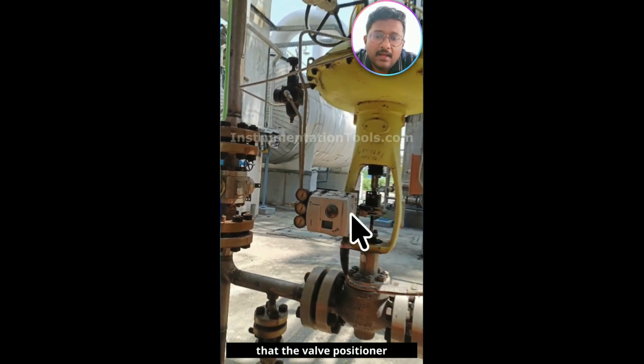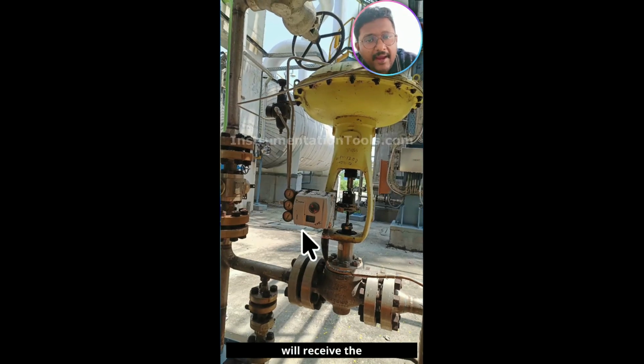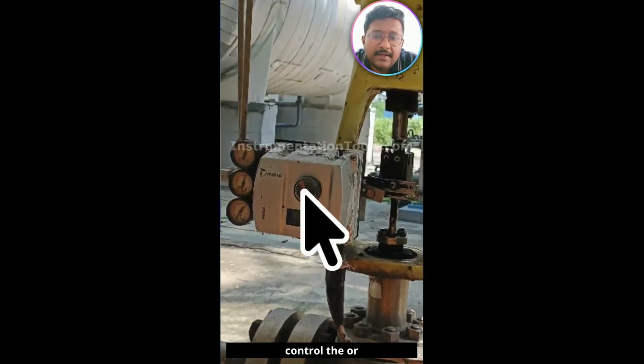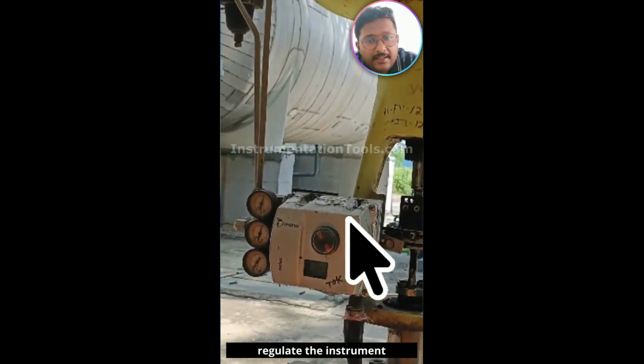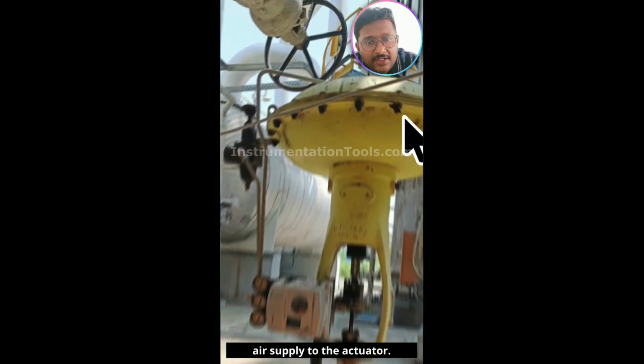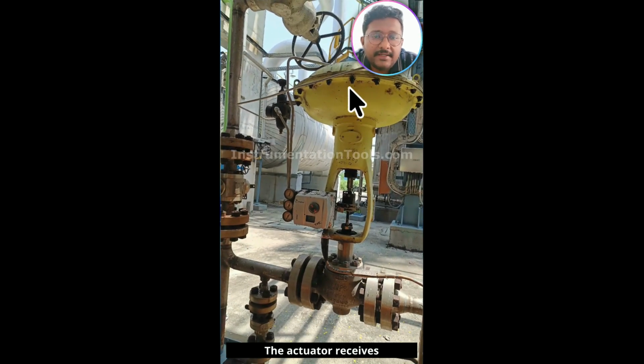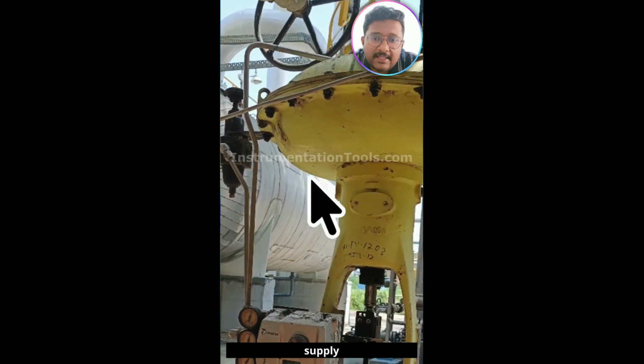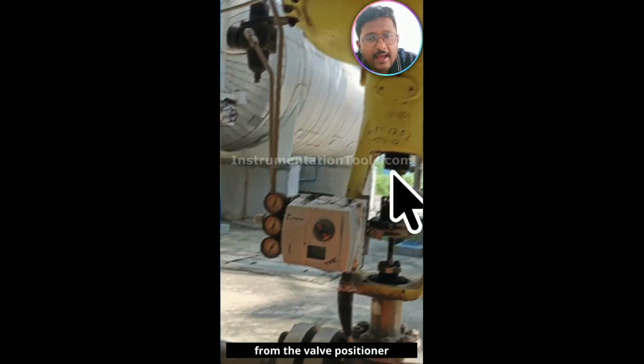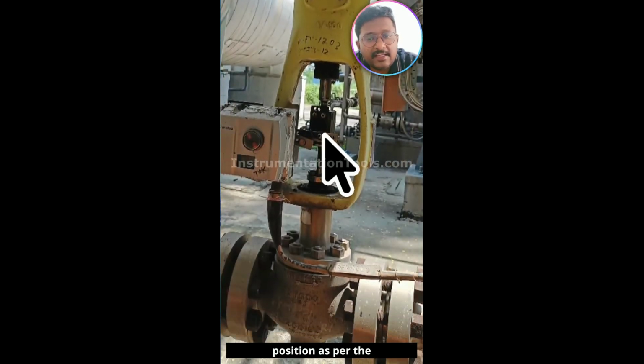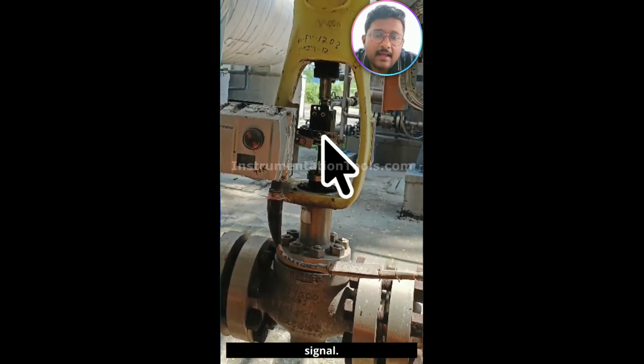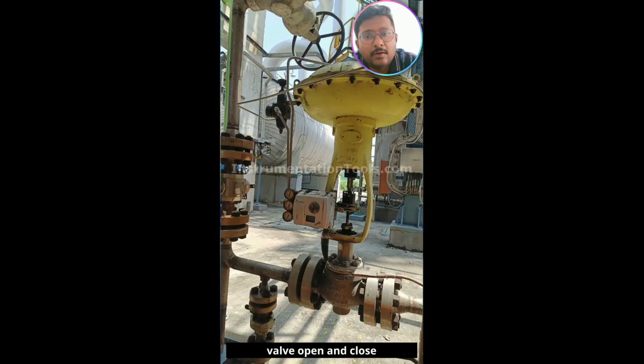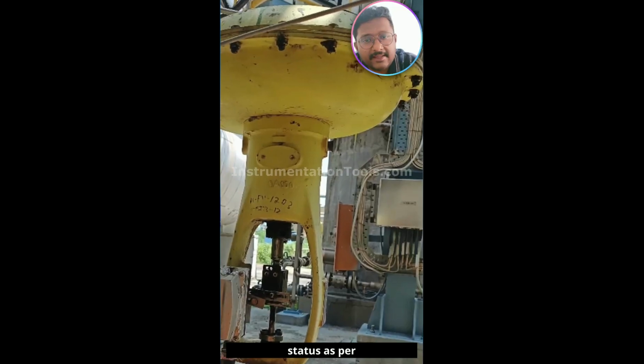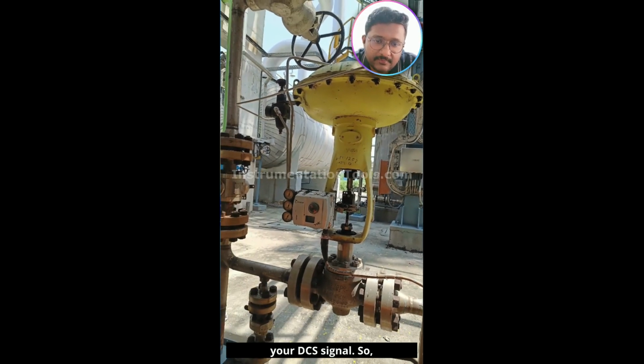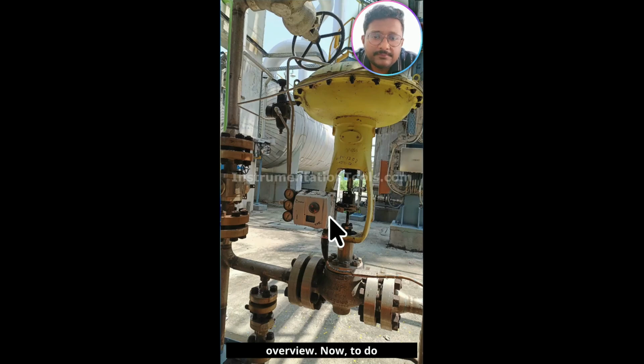Remember that. The valve positioner will receive the command from the DCS system, and as per the command, it will control or regulate the instrument air supply to the actuator. The actuator receives this instrument air supply from the valve positioner and then moves the stem position as per the signal. Then you can control the valve open and close status as per your DCS signal. So this is the basic overview.